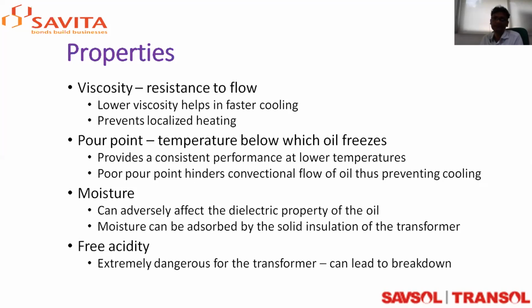Everybody knows the viscosity of oil matters: the lower the viscosity, the better the conduction of heat, which is a primary function of the oil, to cool it. It takes heat from the oil to the fins of the transformer, where it dissipates from the fins to the air because of forced or natural circulation. There are always hot spots in the transformer with high temperature. The oil takes away the heat generated at the local hotspot and dissipates it throughout the oil as quickly as possible if the viscosity is low, preventing further increase of temperature.